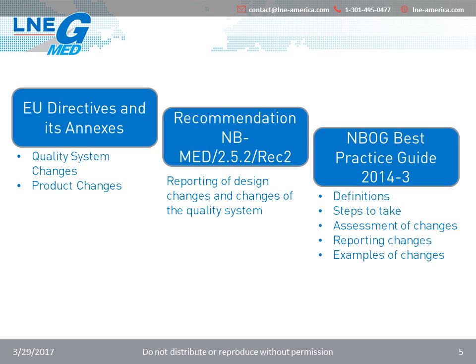The recommendation NBMed 2.5.2 and the Best Practice Guide 2014-3 provide information in terms of reporting of the design changes and the changes of the quality system, and also the steps to take and information regarding the assessment of changes by the notified body. The NBOG document also provides examples of changes.